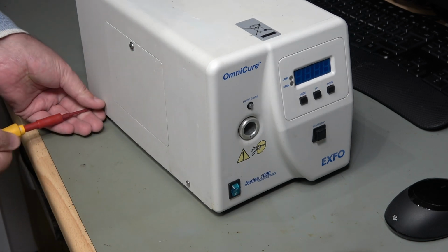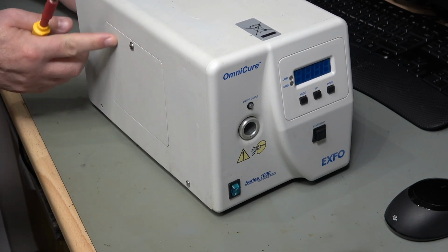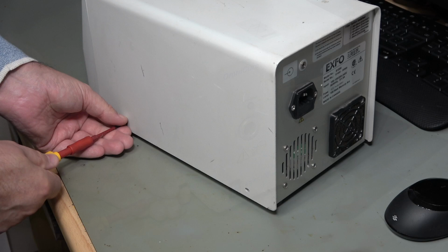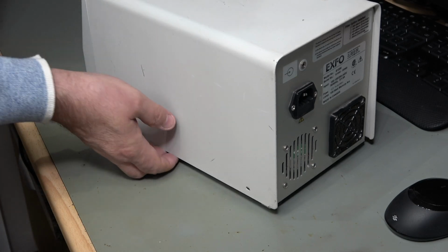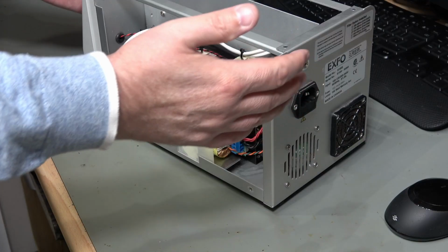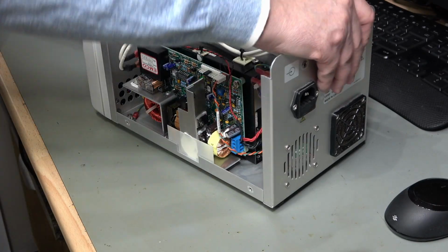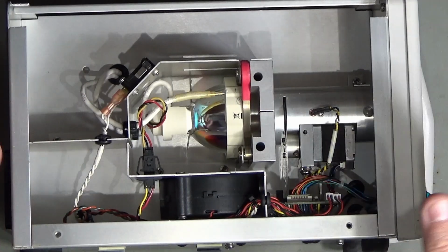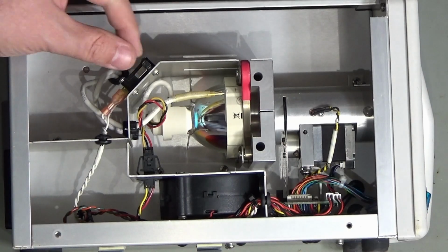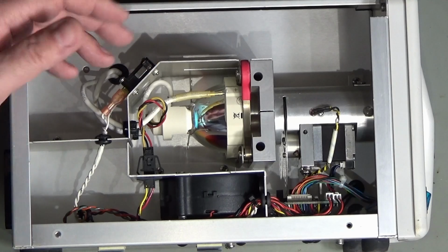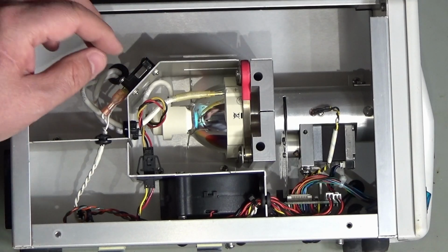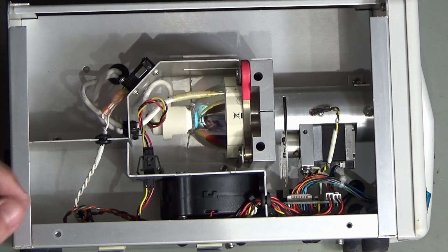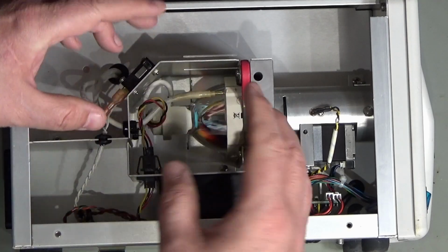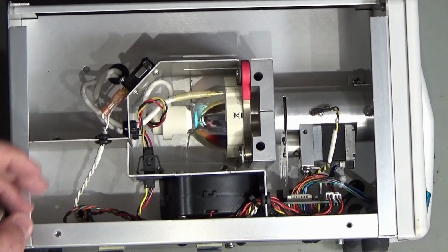Okay, enough talking, let's get it open. So it's just got 4 Phillips screws. This panel here, by the way, is in case you need to change the light bulb. So here we go. Let's take a look at this side first, I think. So this is the optical assembly side. So just here we've got an interlock switch, so I can't operate this now that I've actually taken the lid off, which is a nice safety feature, of course, and that will operate with just the panel that enables you to change the light bulb.